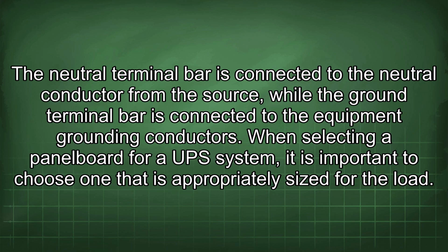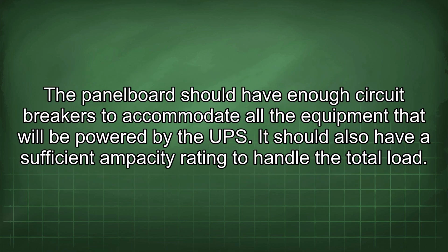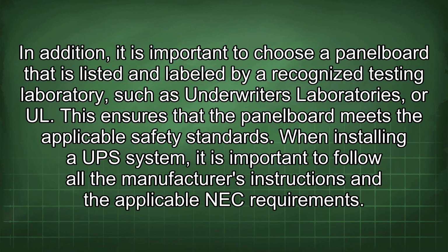When selecting a panel board for a UPS system, it is important to choose one that is appropriately sized for the load. The panel board should have enough circuit breakers to accommodate all the equipment that will be powered by the UPS. It should also have a sufficient ampacity rating to handle the total load. In addition, it is important to choose a panel board that is listed and labeled by a recognized testing laboratory, such as Underwriters Laboratories or UL. This ensures that the panel board meets the applicable safety standards.